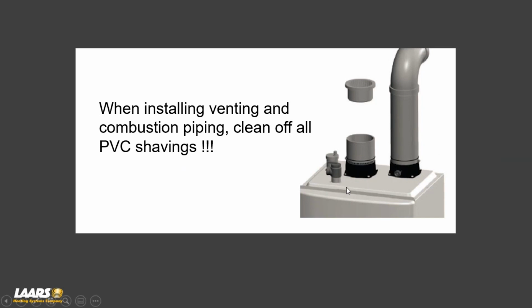Once the blower for the appliance comes on, they get sucked right into the blower and then spit into the burner. And in some cases, you can turn the appliance on, and all of a sudden you hear them mixing around inside that blower cage. Okay. Good practice: wipe those down because they can end up in your burner. So with that, one of the reps had asked that we show how to remove the burner. This is a 199 that I'm going to show you next.